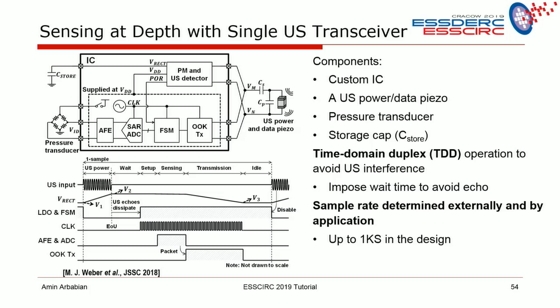Then we start, this is the end of ultrasound, EOU. Then there's a setup time, there's a sensing time, and then we send out the data. So all of that repeats every millisecond. So every millisecond we measure pressure and we transmit out. Every time we get a command to measure pressure, fully asynchronous, it measures the pressure in a millisecond and transmits it out. So this is how this particular implant works, and it's fully time multiplexed between transmit and receive. One piezo does both.